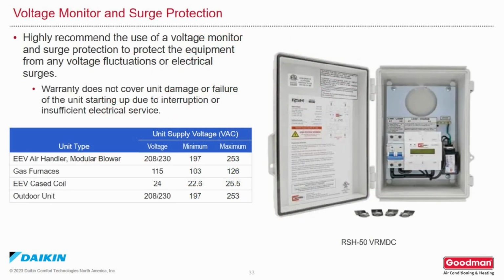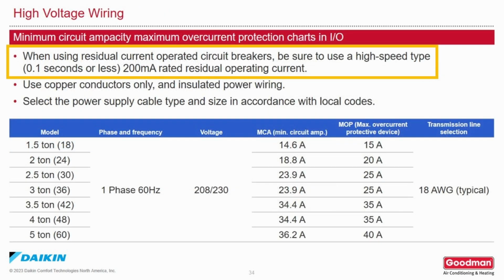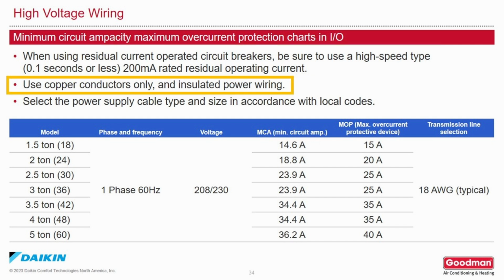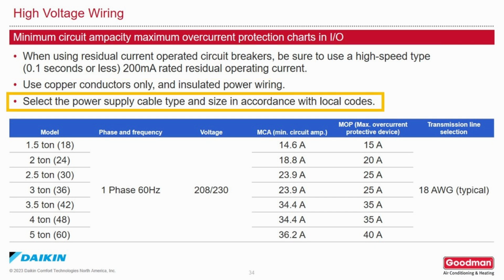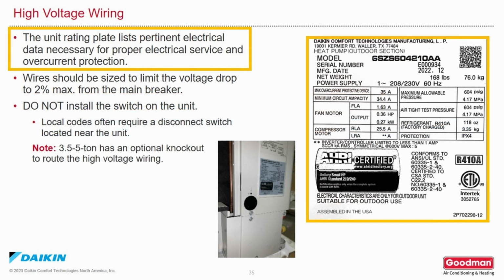It is highly recommended that a voltage monitor and surge protection device is used to protect the equipment from voltage fluctuations or electrical power surges. Here is a list of minimum circuit ampacity and maximum overcurrent protection devices recommended for each size unit. Always use insulated power wires with copper conductors. Size power wires in accordance with your local codes. Pertinent unit electrical information is listed on the data tag on the unit.